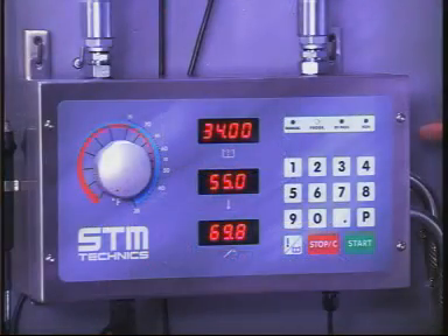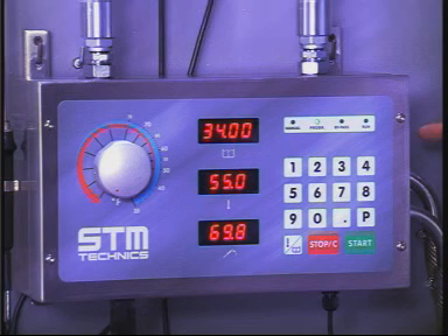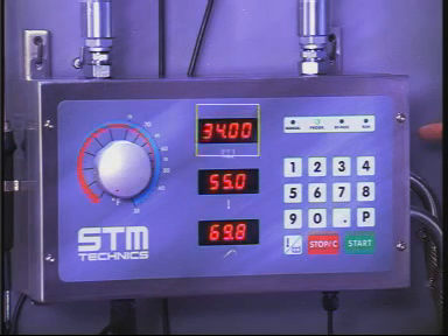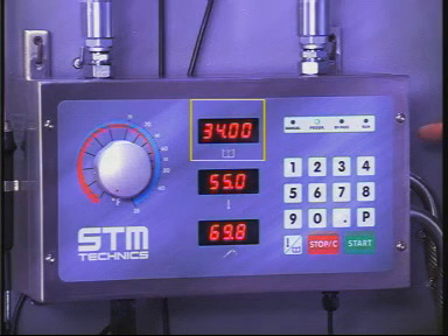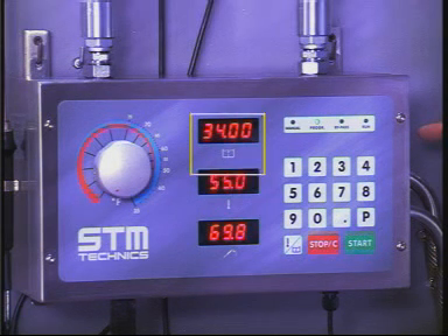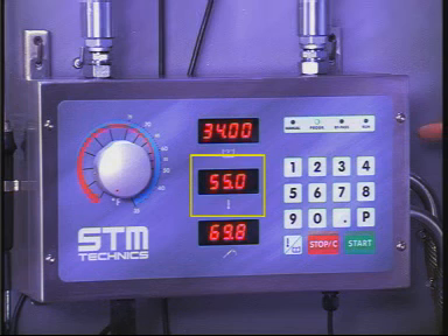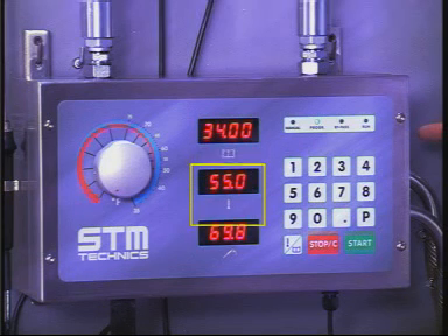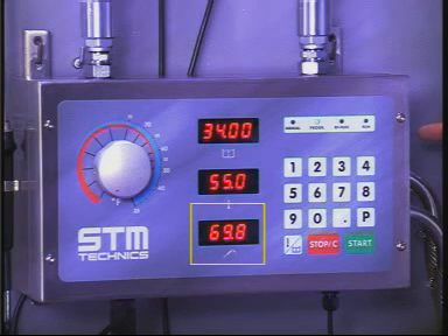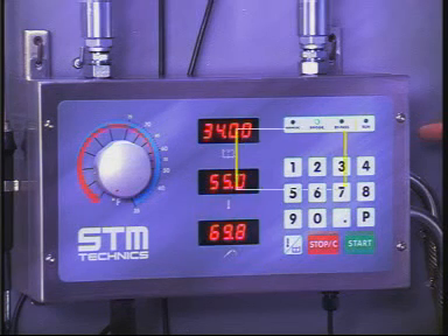The machine container is made of stainless steel or plastic, which consists of a box and a cover. On the cover there is a membrane keyboard with 3 digital displays. The one at the top shows the quantity of water to be discharged. The one in the middle shows the temperature at the internal probe, and the one at the bottom shows the temperature at the external probe.